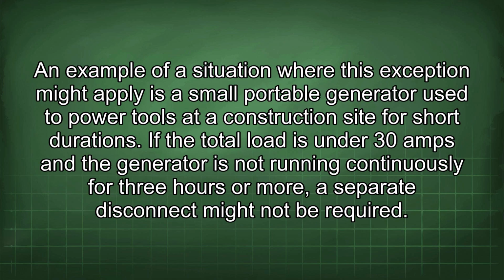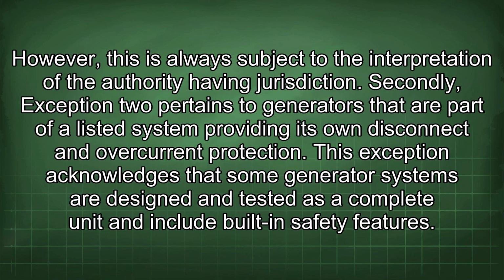An example of a situation where this exception might apply is a small portable generator used to power tools at a construction site for short durations. If the total load is under 30 amps and the generator is not running continuously for 3 hours or more, a separate disconnect might not be required. However, this is always subject to the interpretation of the authority having jurisdiction.